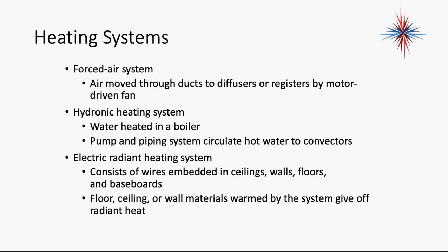A forced air heating system moves air through ducts to diffusers or registers by a motor-driven fan — a blower motor, nine times out of ten a PSC (permanent split capacitor) motor. With hydronic heating systems, water is heated in a boiler, and a pump and piping system circulates hot water to convectors — the radiators you see along the floor or the big cast iron radiators — depending on the age of the building.